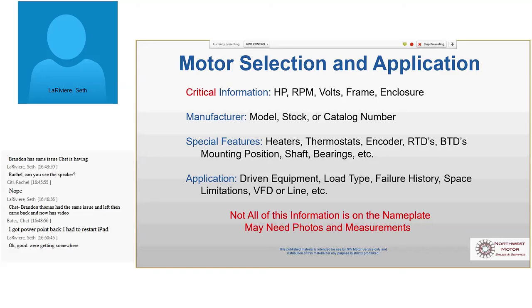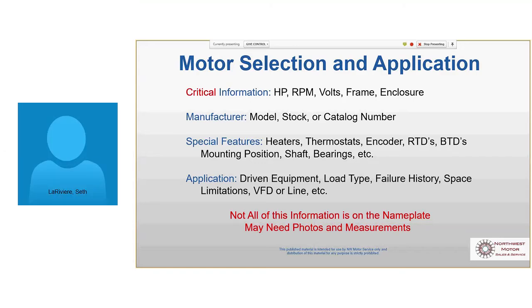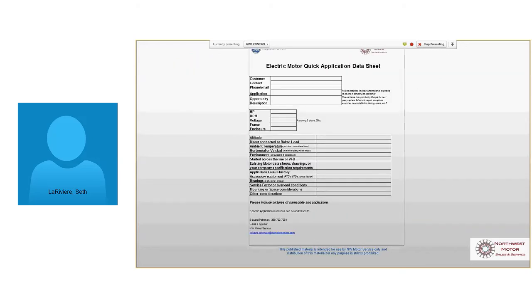So a lot of this stuff you'll get off the nameplate, some you won't, like the load, because the manufacturer wouldn't know that, right? So they wouldn't put that on the nameplate. So if you can tell us a little bit about if it's on an unusually high inertia fan or anything like that, a hard to start compressor, those sorts of things are helpful. There are different motor designations, and we're going to talk about that in a minute on torque. And this is a sheet that can be of use, a little data sheet to help you collect the right information.